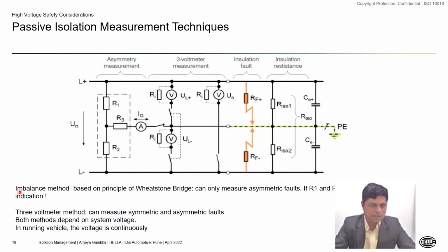In the first method, which is called an imbalance method, it is based on the principle of Wheatstone bridge. You can see R1, R2, and R3 resistors. The disadvantage of this system, though it looks very simple in implementation, is it can only measure asymmetric faults. If the value of R1 and R2 is exactly the same, then there is no way possible to find out if there was a leakage because of RF plus or RF minus or both. Then the next method is the 3 voltmeter method, which was also very popular in the industry. Basically this method has these three switches and these 3 voltmeters. I will discuss more about this method in the next slide.